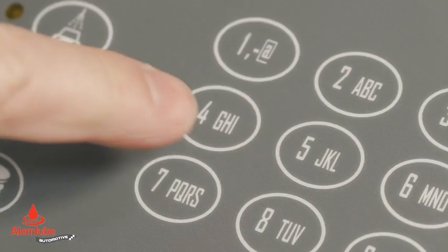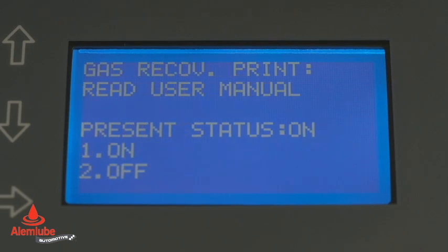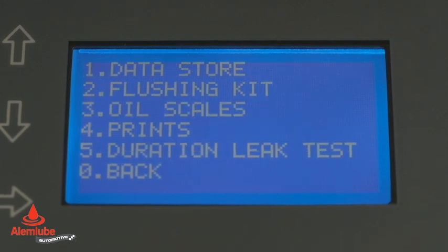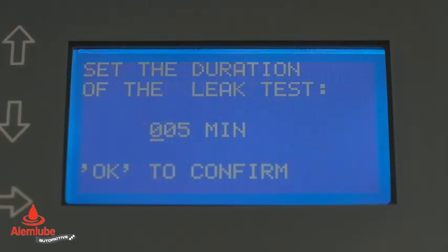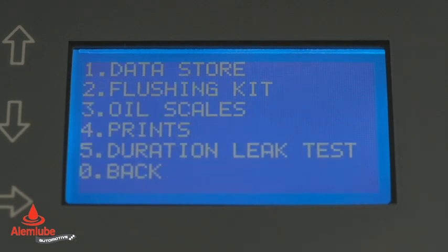By typing 4 it is possible to decide whether to print the quantity of gas recovered in the automatic function. By default the recovered gas printing is activated. By typing 5 it is then possible to select the duration of the vacuum test. It's 5 minutes by default. Any value can be set as long as it is greater than 5 minutes. By typing 0 we go back to the previous menu.